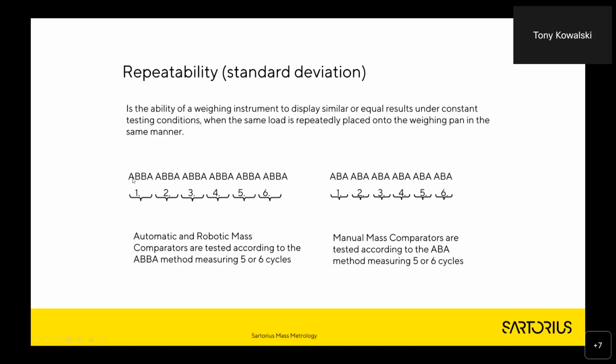So we can use the reference weight with its test weight, and when we place the reference weight on again, we have another value for the test weight. So basically, in the first difference, each time we place the reference weight, it has its own B. So each A has its own B that is being compared against. So this A is compared against this B, this A is compared against this B. And because there's more readability or resolution, there may just be a little bit more drift.